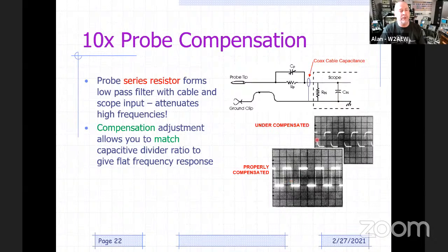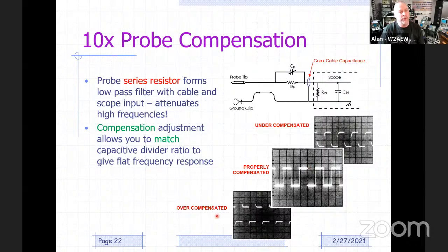If it's not properly adjusted, if it's undercompensated, like if this capacitor was too small, then you'll make the edges slower, and it'll look like this. So you adjust that to properly compensate. If the capacitor is adjusted the other way, you'll be overcompensated, right? And you may overshoot the signal. That's when this capacitor is actually too big. You'll overshoot the signal.